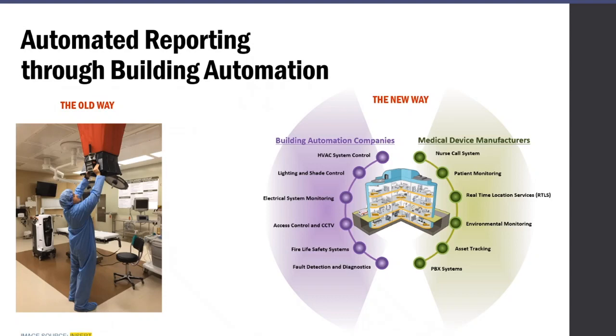So Frank and I have been working on this concept for 1.5 years or more, probably close to 2 years. The whole idea is having automated devices within the duct that read the airflow, rather than having to go up with a hood and read it. We're going backwards. CMS, the feds, require all critical care areas to be verified every year. Facilities are paying upwards of $75,000 to $100,000 every year just for the critical care areas to balance.